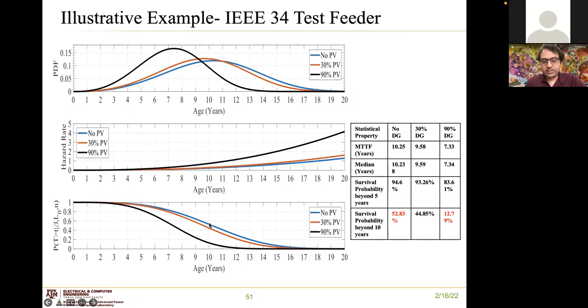Looking at hazard rates, with higher DG in the system the probability of an immediate failure also increases. And looking at the survival plots, with 90% PV, for example, the survival probability beyond 10 years drops to roughly 10% from 50% in the no-PV scenario. So there is a significant reduction in the lifetime of these devices at high penetrations of distributed generation.